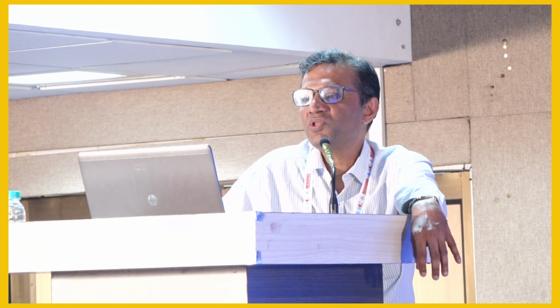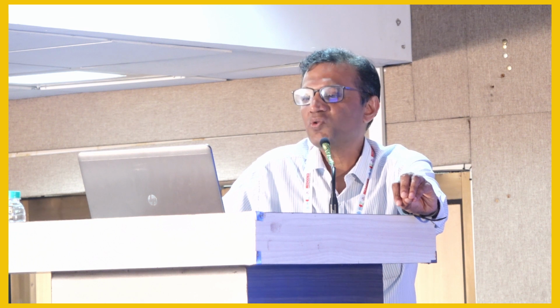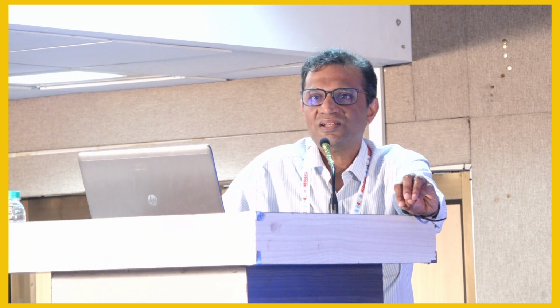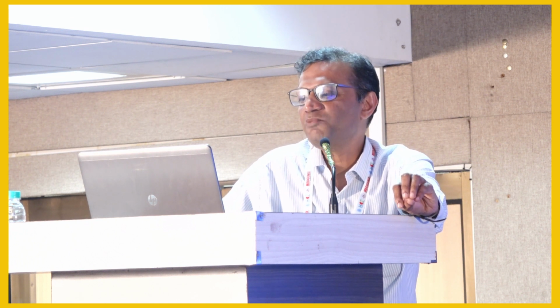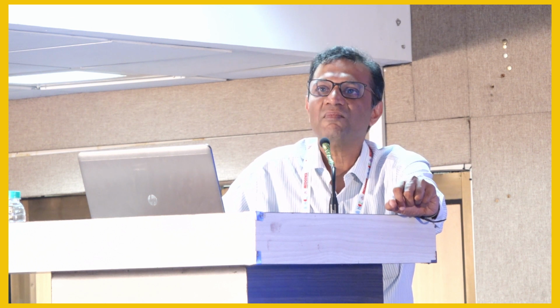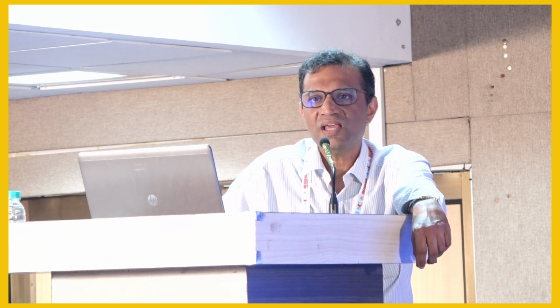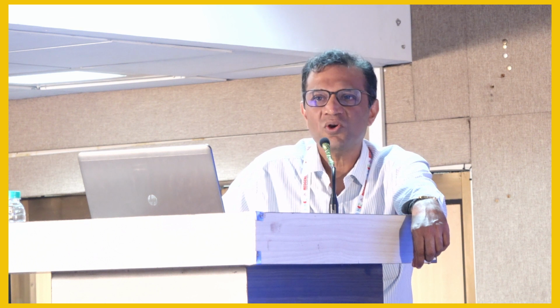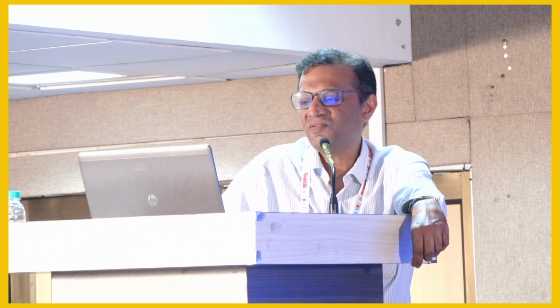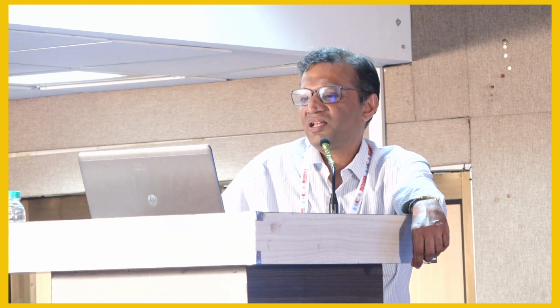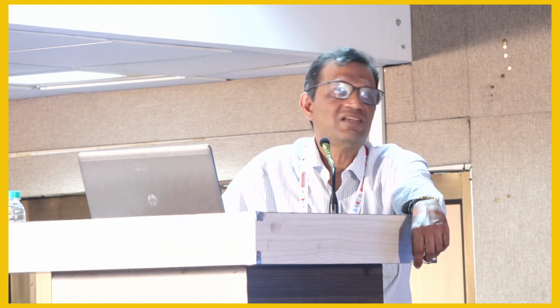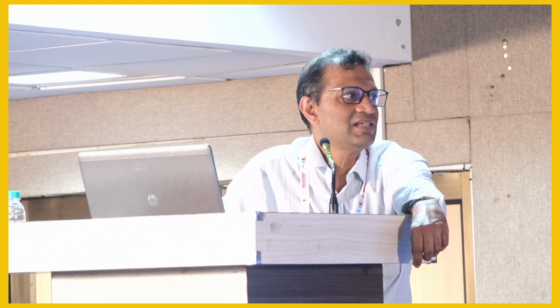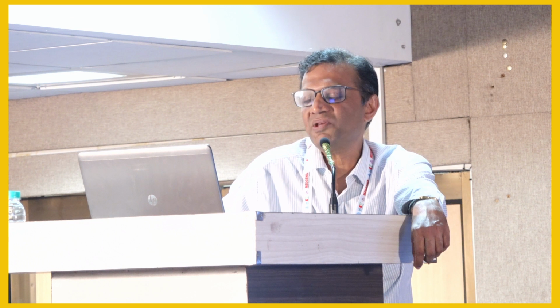If we are to do this, the self-test in which the machine tests its safety system should never ever be bypassed. The guidelines say the alarm should be visible from at least 2 meters and about 70 decibels. I say the alarm should be so irritating that you cannot ignore it. You are forced to go and deal with the alarm condition. And so you would never want to see this message on your machine. It says test override and the test lamp is flashing.